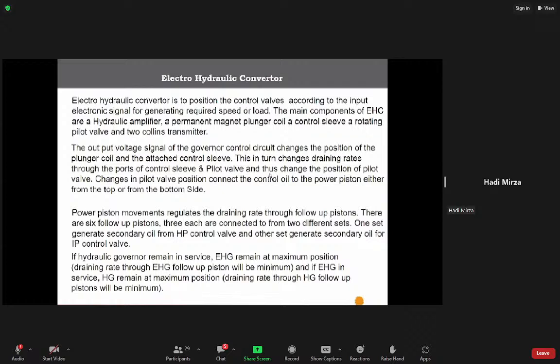This in turn changes the draining rate through the ports of the control sleeve and pilot valve, and thus changes the position of the pilot valve. Changes in pilot valve position connect the control oil to the power piston either from the top or from the bottom side. That is what I have already said in the previous slide. Piston movement regulates the draining rate through the follow piston. There are 6 follow pistons. Basically, in 600, there are 4 follow pistons, 2 in each IP and HP.